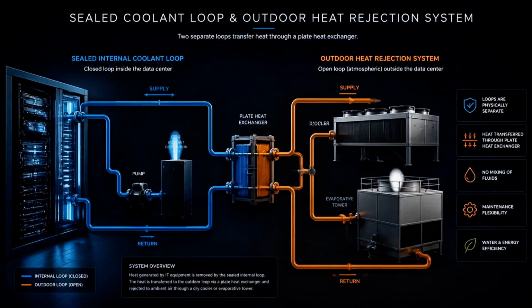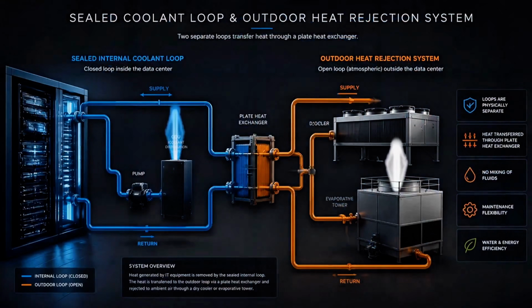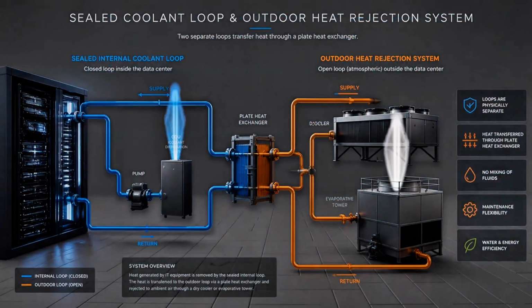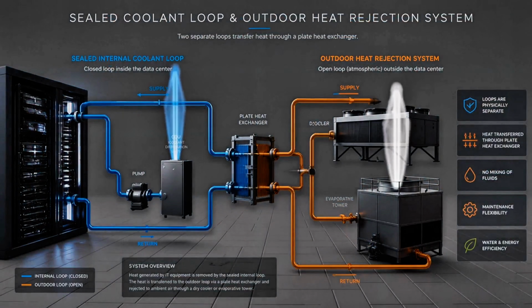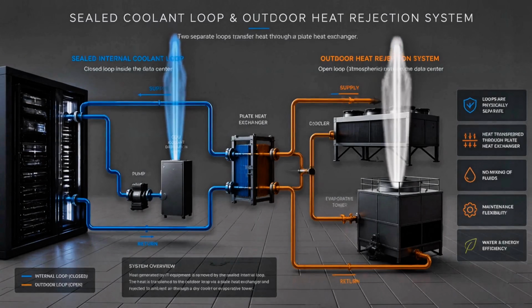Liquid cooling does not automatically mean that water is constantly consumed. Internal coolant loops can be sealed and recirculated. Actual water use depends mainly on how the facility rejects heat outdoors. A dry cooler uses air, while an evaporative cooling tower may consume water to save energy.